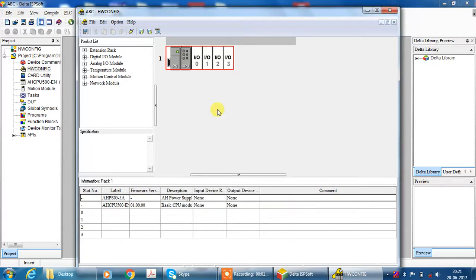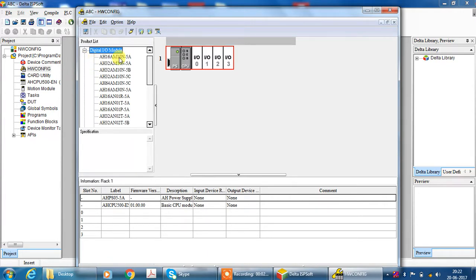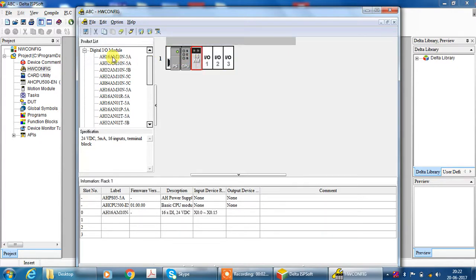I can configure 4 digital inputs, digital output, analog input and analog output. For programming I select 32 input and 32 output digital. I will choose first digital input — simple drag and drop. Second time drag and drop, here 2 modules digital input is configured. Address is starting from X0.0 to X0.15 and X1.0 to X1.15. 32 inputs ready for programming.